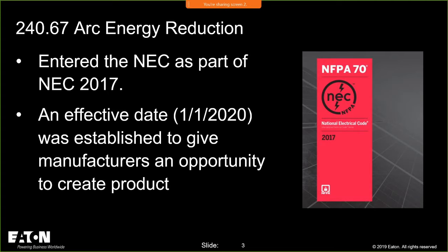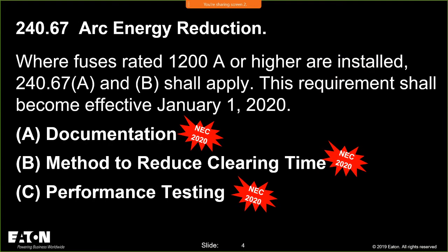So 240.67 entered the code as part of the 2017 cycle with an effective date of January 1st, 2020. What that did was, there was one manufacturer who had a solution, and the desire of the panel was to make sure that all manufacturers had some time to come up with solutions. So the way the language reads, it says where fuses rated 1200 amps or higher are installed, so it's keyed off of the fuse, A and B apply, which we've got to modify, for my fellow Panel 10 members. It should be A, B, and C.